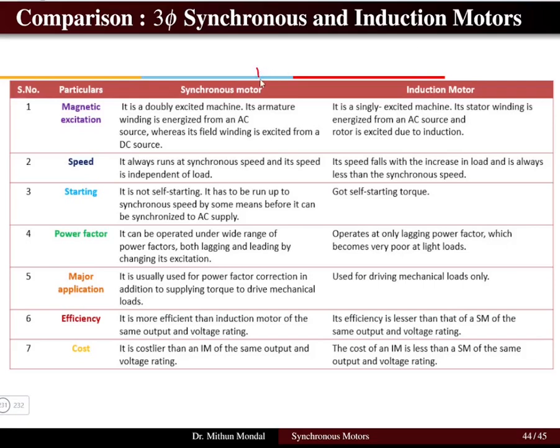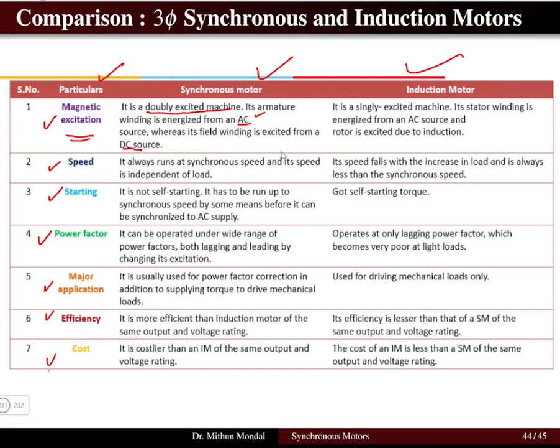Having known the merits and demerits, we now compare the three-phase synchronous motor and three-phase induction motor based on characteristics such as magnetization, speed, starting method, power factor, application, efficiency, and cost. Regarding magnetic excitation: the synchronous motor is a doubly excited machine requiring both a DC source for field winding and an AC source for stator winding, whereas the induction motor is a singly excited machine — its stator is energized from AC and the rotor is excited by induction, requiring no DC source.